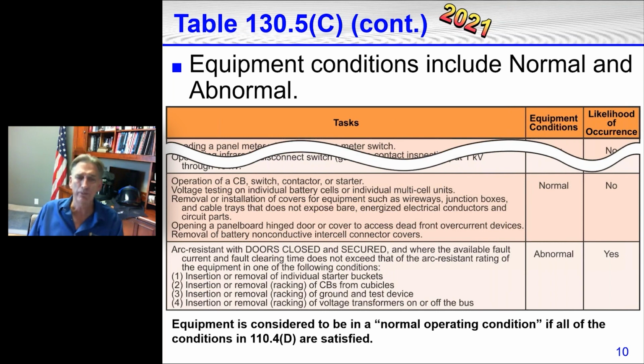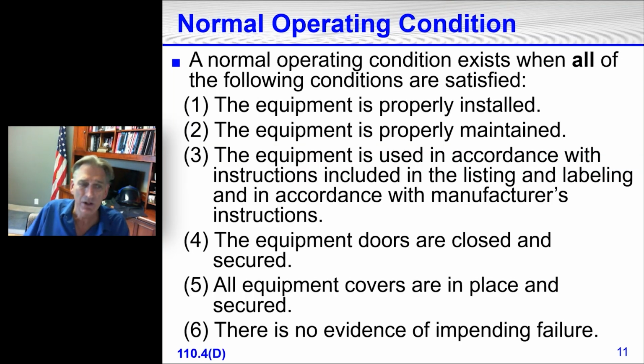All right, so what is normal operating condition? And these are the conditions. A normal operating condition exists when all of the following conditions are satisfied. The equipment is properly installed. The equipment is properly maintained. The equipment is used in accordance with instructions included in the listing and labeling and in accordance with the manufacturer's instructions. All right, for us guys that are in the webinar today, I know, and you probably know as well, we have a hard time reading instructions, right? So, and much less complying with them. Sometimes we don't even like reading the instructions. But anyway, that's what's required for the equipment to be in normal operating condition.